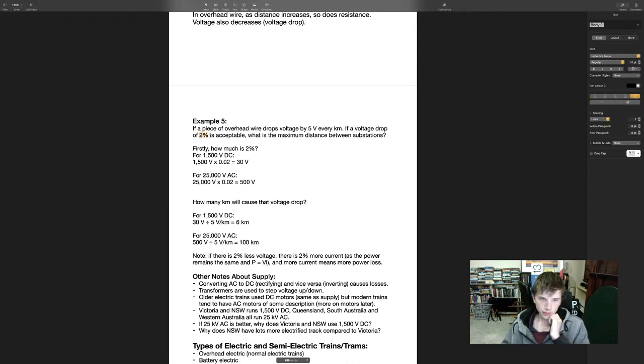But I mean, why this 2% to begin with? Well, remember, if there's 2% less voltage, then there is 2% more current, because the power has to remain the same, but power equals voltage times current, so we need them to balance each other out. And more current means more power loss. In fact, if we've got 2% more current, then we'll have 4% more power loss, because remember, current is squared in the power loss formula.